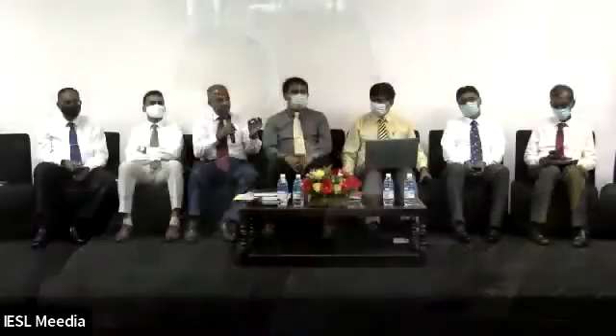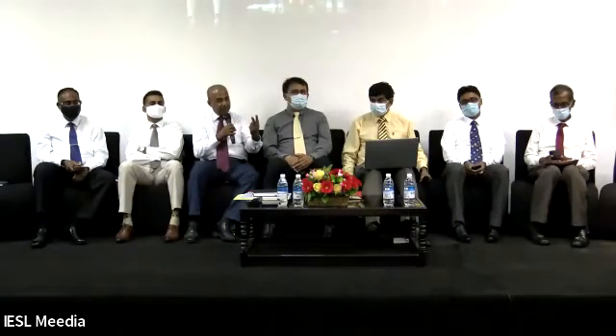Yet, if you look at some of the recent failures, including the 2020 August failure, what has really happened? You can go through the analysis of what happened after the initial incident, but what has really happened is the protection system, reliable as it is, remember, it is redundant. If you take this Kothmale-Biyagama line, there are 2 relays from 2 different manufacturers duplicating all protection functions. That is the level of redundancy that we have in our system. It is the case in all other lines also.